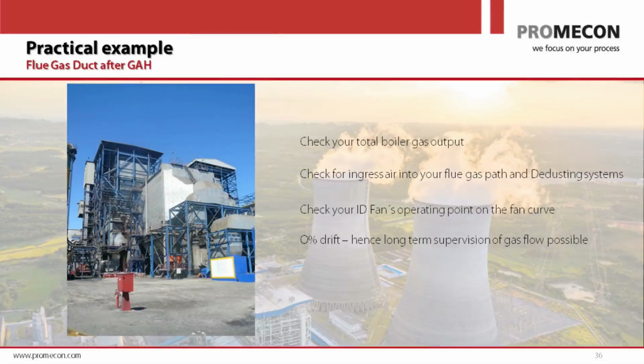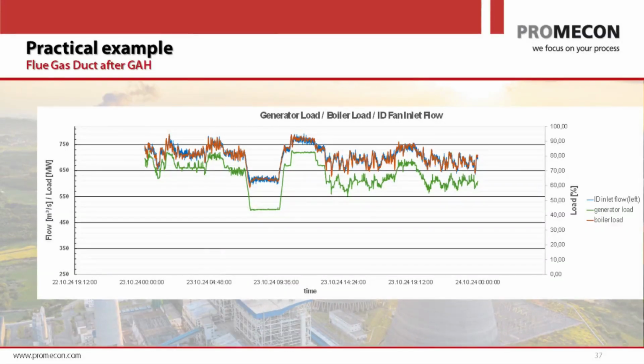Why is that a problem? Of course, the side that pulls more gas usually has the bigger particulate emission problem because the separation of particulate matter is not so easy if you have too high gas flows. So here you can really balance those. Another typical application is if you have, let's say, two boilers and three scrubbers, are all three scrubbers getting the right amount of flue gas? Or is each scrubber getting the correct amount of flue gas? And is it really in line with the amount of lime that we're spraying in, etc.? So there's also a good reason to measure flue gas ducts.